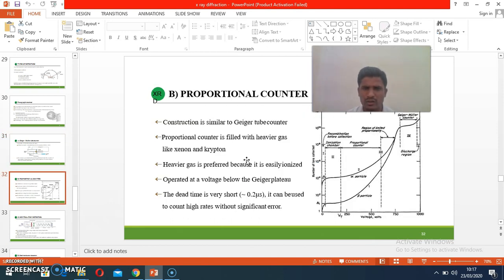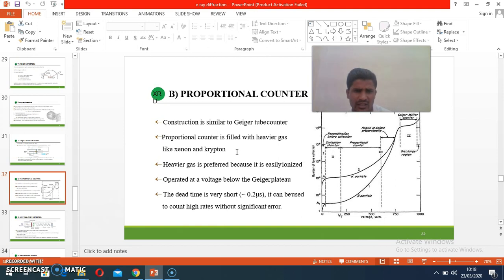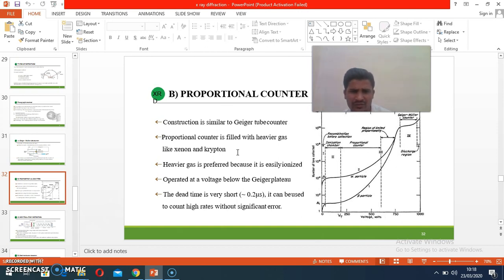The proportional counter works similarly to the Geiger-Müller tube. It is also considered a gas-filled detector. X-rays interact with the gas, causing ionization, and the emission of electrons takes place. These electrons go to the electrode.